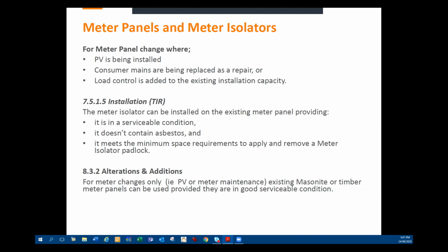7.5.1.5 installation: a meter isolator can be installed on the existing panel provided it's in a serviceable condition, it doesn't contain asbestos and it meets the minimum space requirements to apply and remove a meter isolator padlock. So we've had some issues around this, so it's a bit more of a re-clarification, and this clause basically lines up with 8.3.2 alterations and additions that in the last edition was changed slightly. So basically where there's meter changes only, i.e. PV or meter maintenance, the existing masonite or timber meter panels can be used provided that they're in good serviceable condition.